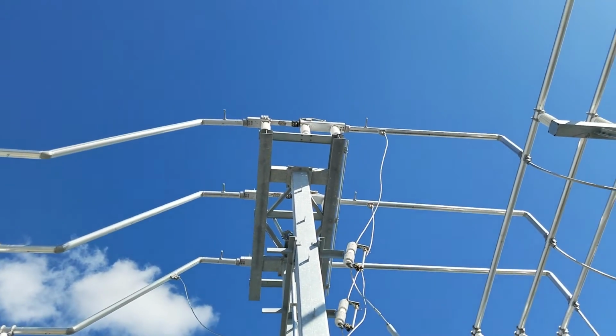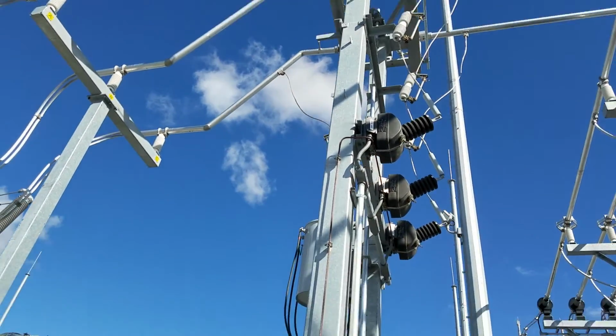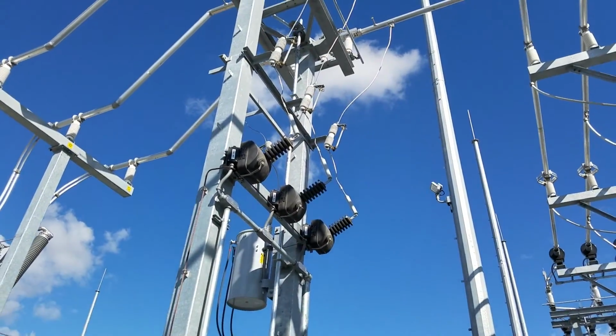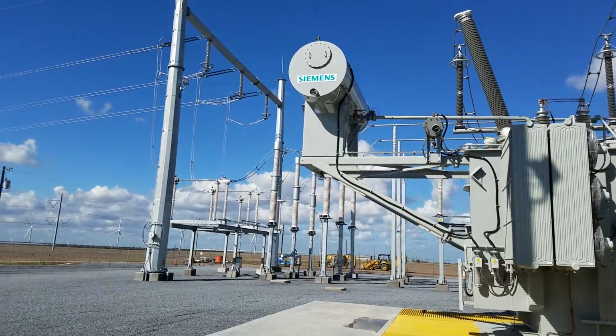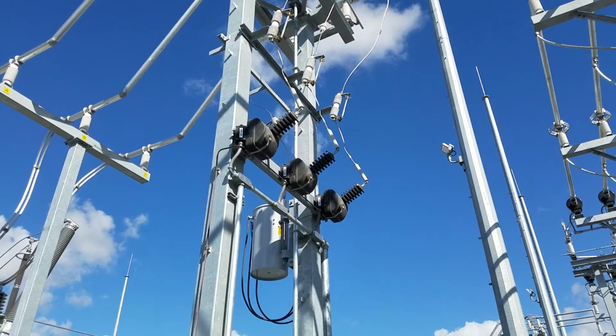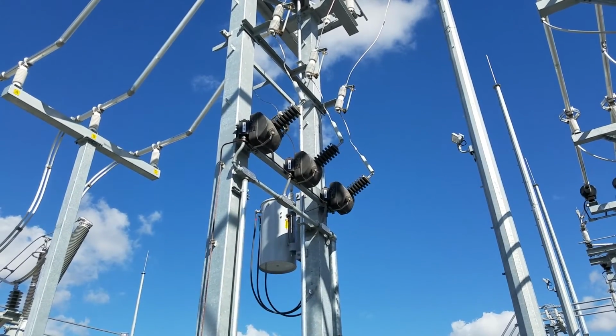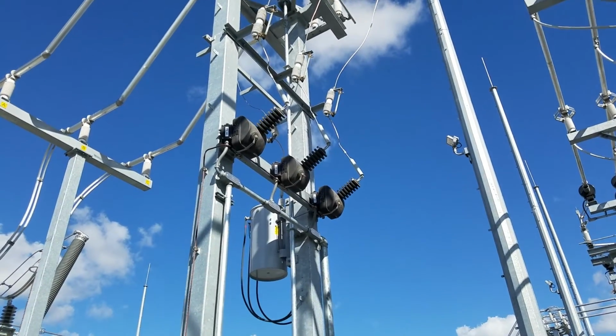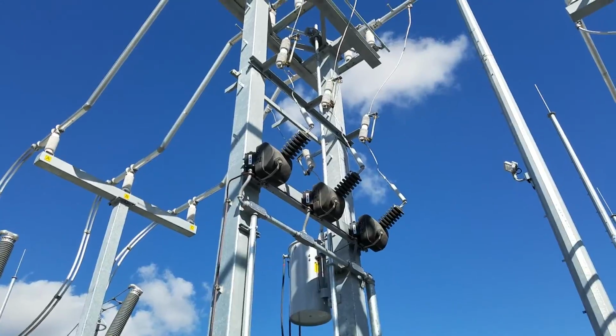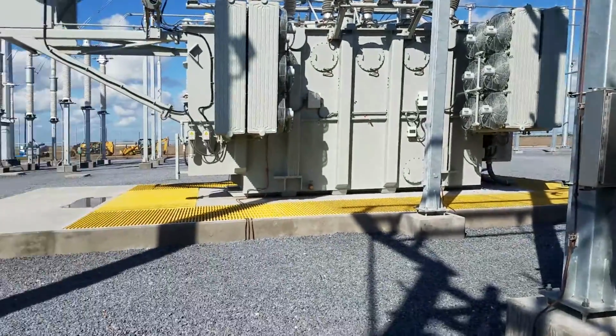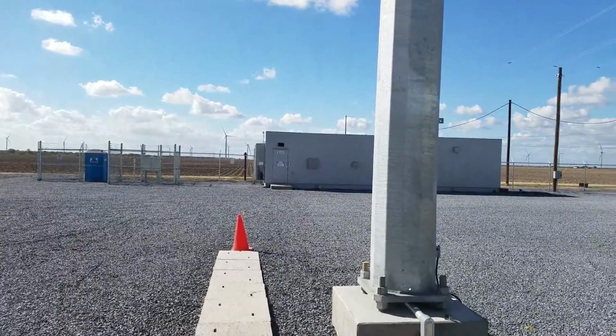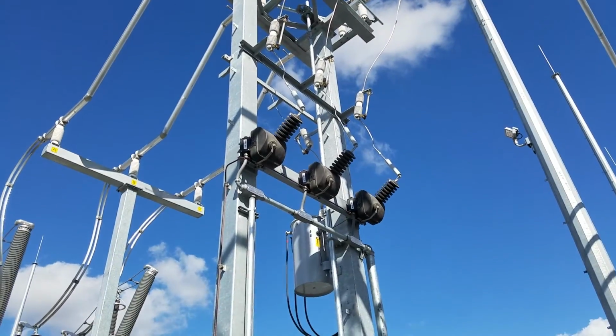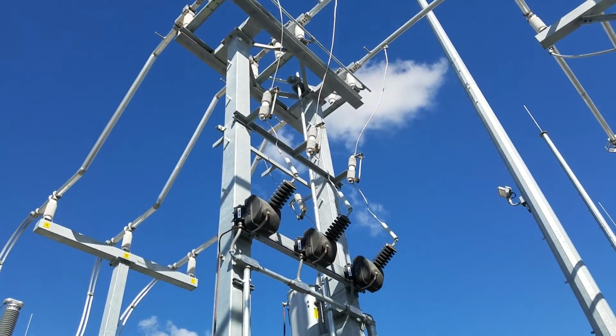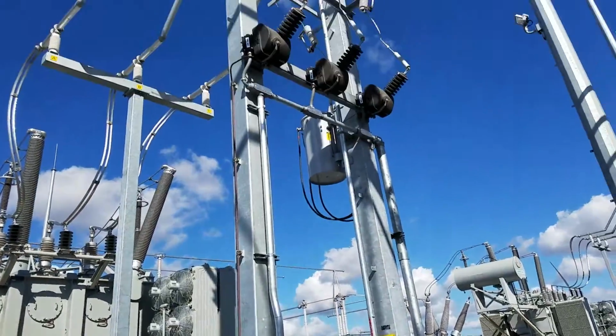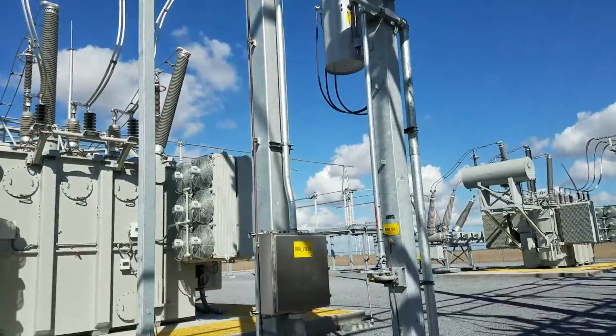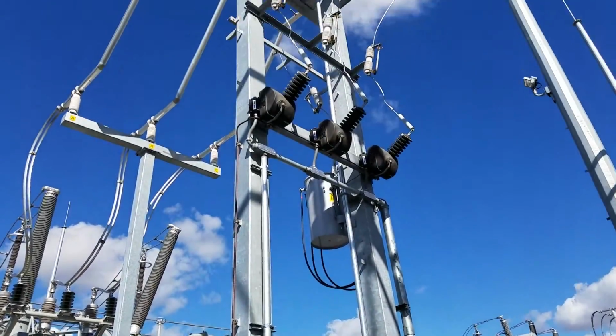So you can potentially have 4 different power sources here. So it goes through a switch, same as that big one, but doesn't need to be as big because the voltage isn't as high. And these here are PTs. Remember the PTs we talked about that were on the other side? Because this is a lower voltage, they don't need to be as big. So the ratio isn't as big, so the transformers aren't as large. But they're basically transformers, but we call them PTs, potential transformers. So that goes to the junction box and goes inside, and that's how we monitor what the voltage is. Again, it's probably the 69 and 115 volts again, so at 34,500 volts, you're going to read 115 volts down here, and say if it goes to 30,000 volts, you probably only read 100 volts down here. So that's how they monitor the voltage.